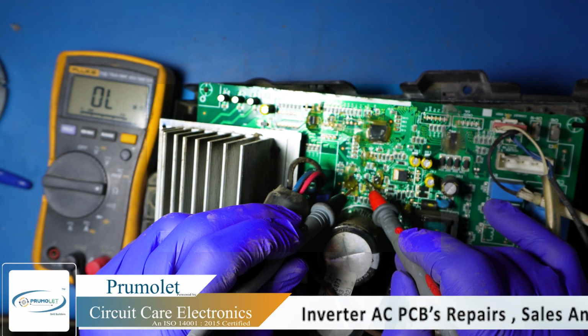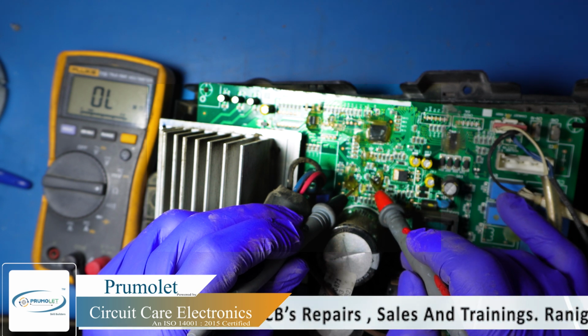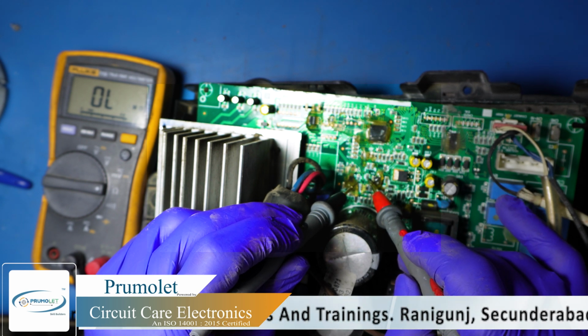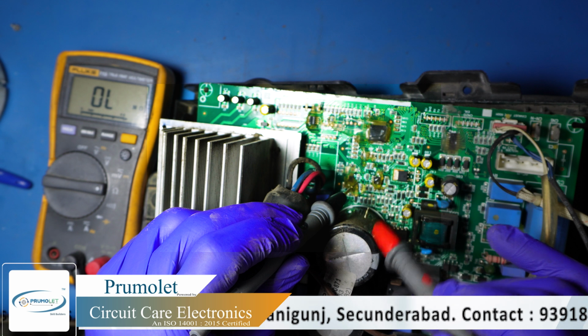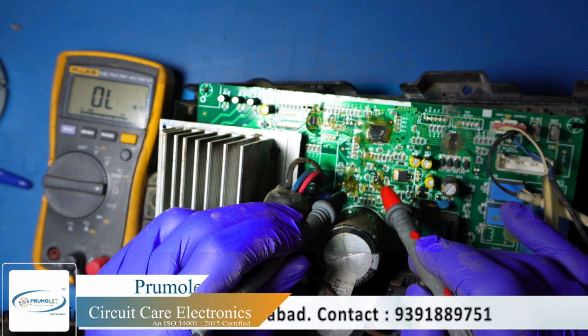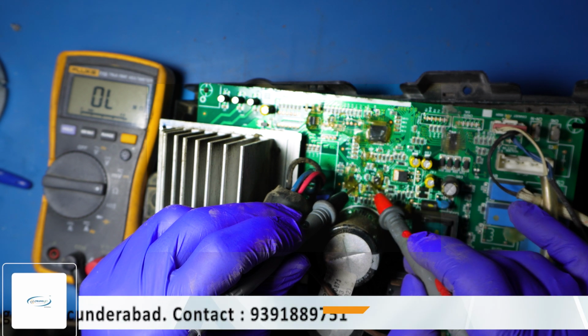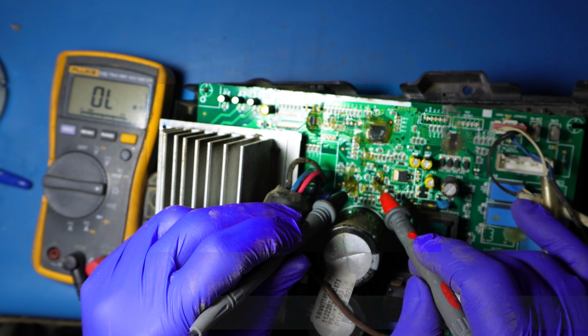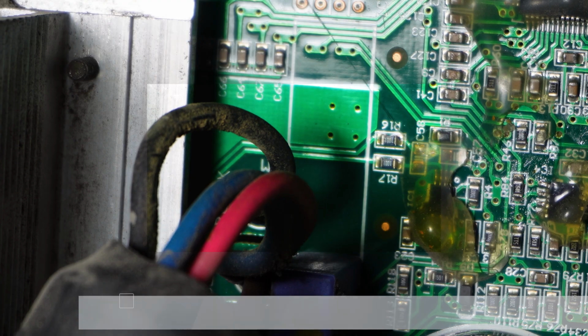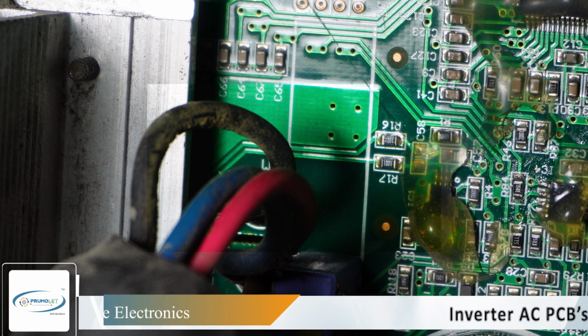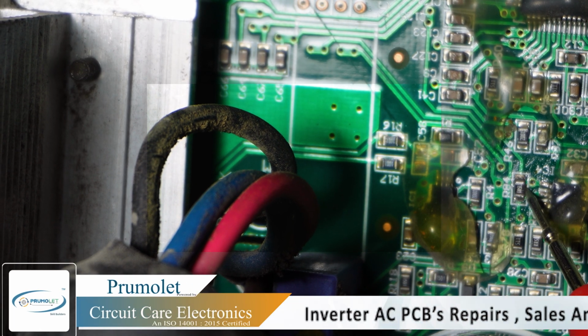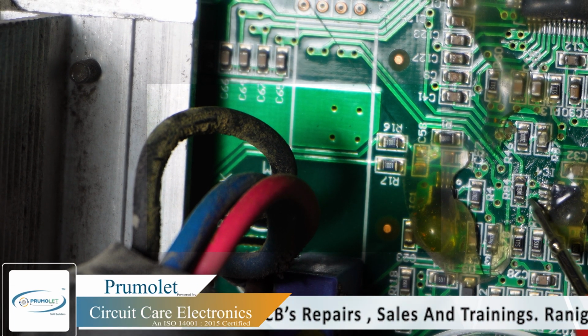So this resistor is failed. Due to that, the reference DC voltage is showing low. Because of the malfunction of this resistor, the reference voltage is showing low. I'll show you the resistor. Hope it's clear now. This resistor is 7.5K.